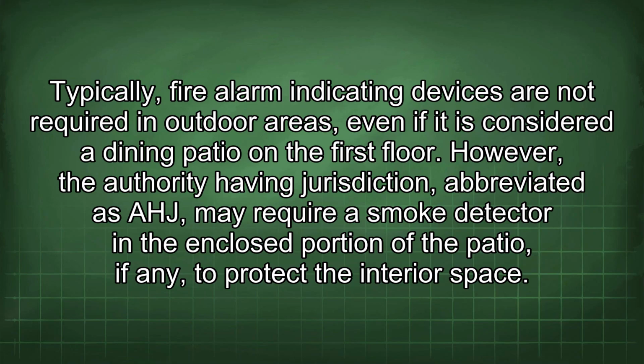Typically, fire alarm indicating devices are not required in outdoor areas, even if it is considered a dining patio on the first floor. However, the authority having jurisdiction, abbreviated as AHJ, may require a smoke detector in the enclosed portion of the patio, if any, to protect the interior space.